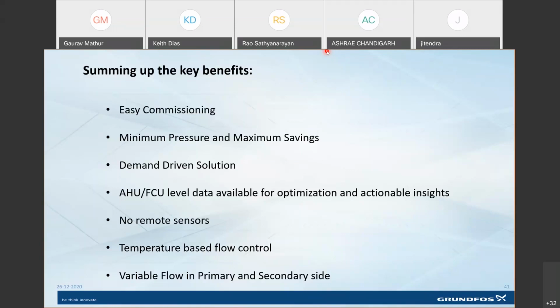The second last point is the temperature-based flow control, and it's really amazing that the entire circuit is running on temperature-based control. The entire control of the chiller is on temperature. And the moment you have a pressure-based control combined with a temperature-based control, there is a limitation on the amount of savings which are possible. One of the reasons why you have seen that the system curve in a distributed pumping was not changing is because of this temperature-based control. And that is an essential benefit which you get.